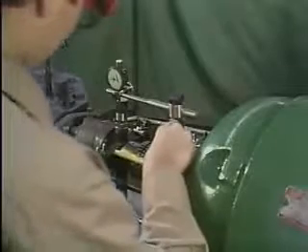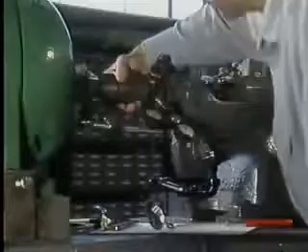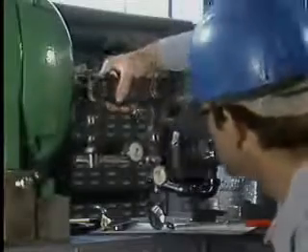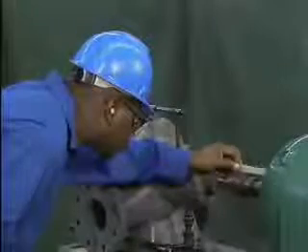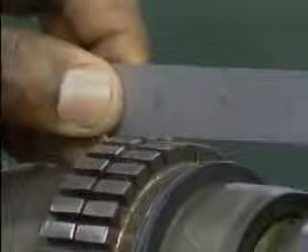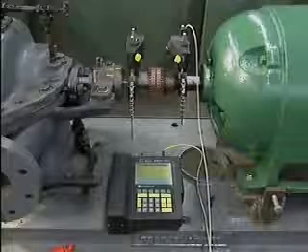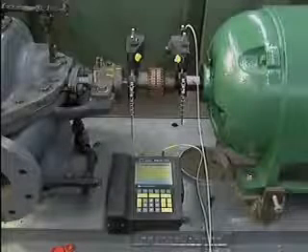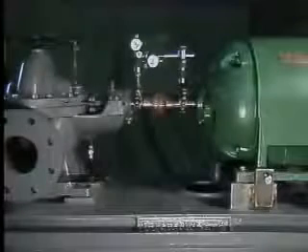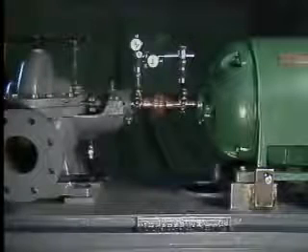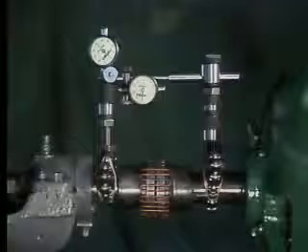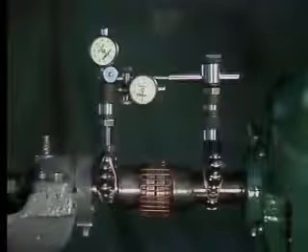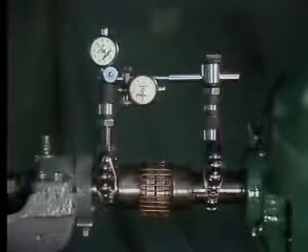Correcting misalignment requires a number of measurements. And the way those measurements are made depends on the type of alignment procedure being used. Some alignment techniques use only a straight edge and a feeler gauge. Others rely on complex instruments such as laser alignment equipment. But often, measurements are made with dial indicators. Two types of dial indicators are generally used for alignment work, the balanced type and the continuous type.